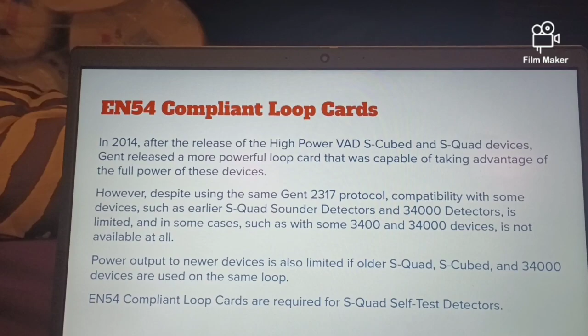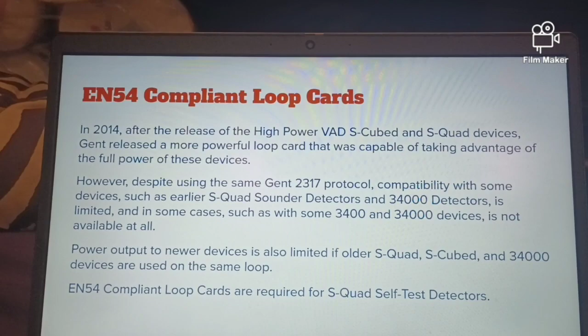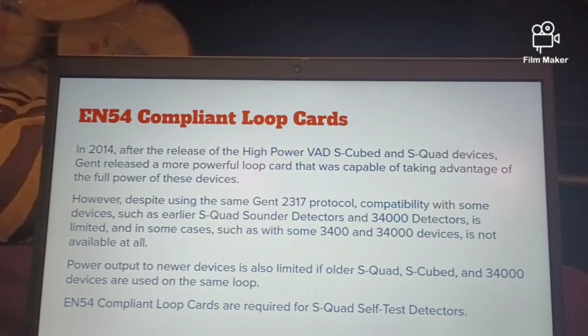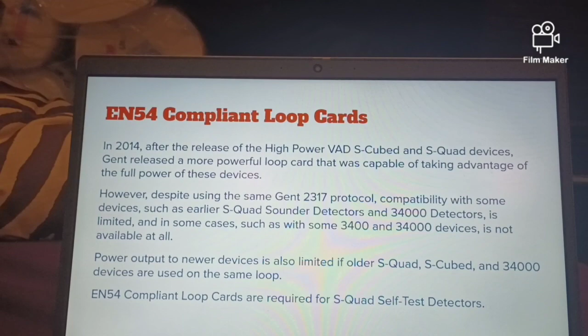EN54 compliant loop cards. In 2014, after the release of the high-power S-Cubed and S-Quad devices, Gent released a more powerful loop card capable of taking advantage of the full power of these devices. However, despite using the same Gent 2317 protocol, compatibility with some devices, such as earlier S-Quad sounder detectors and 34,000 detectors, is limited.